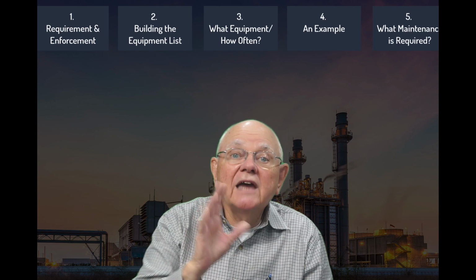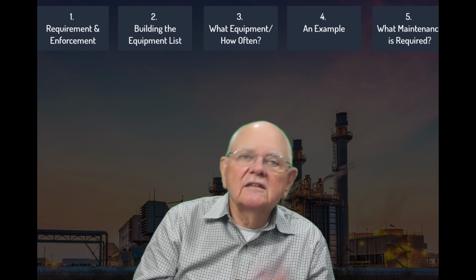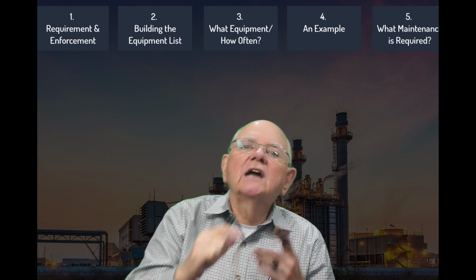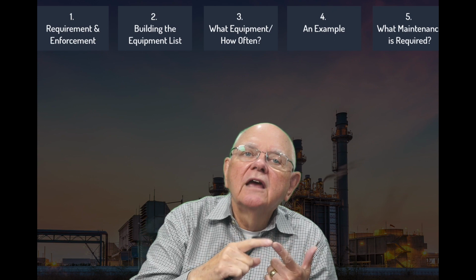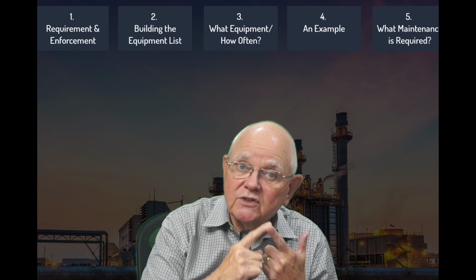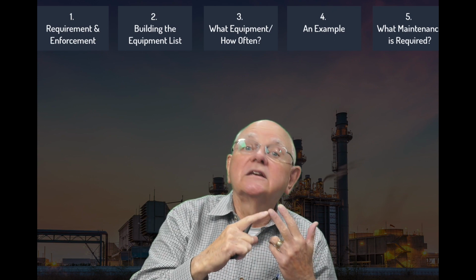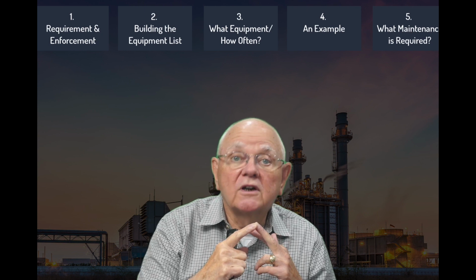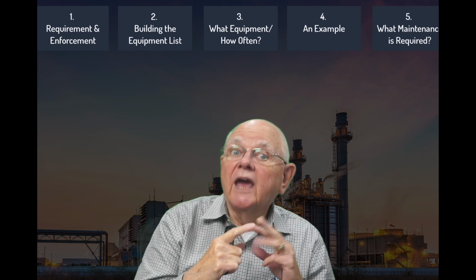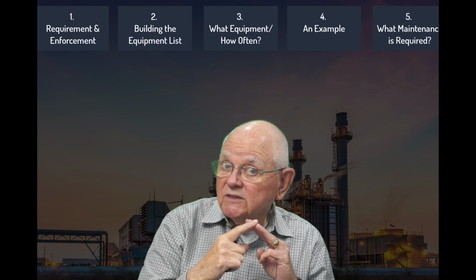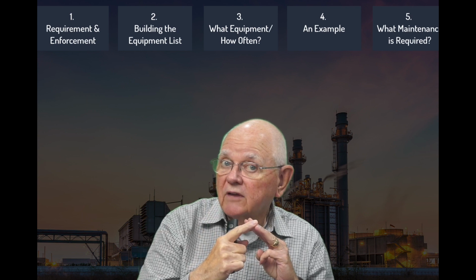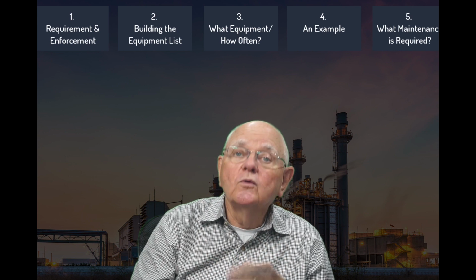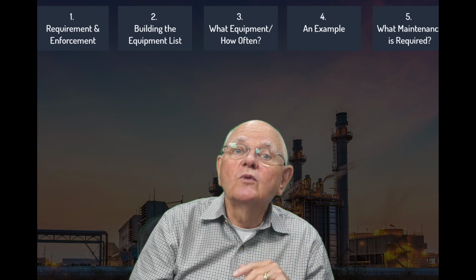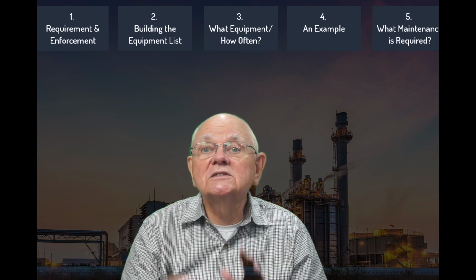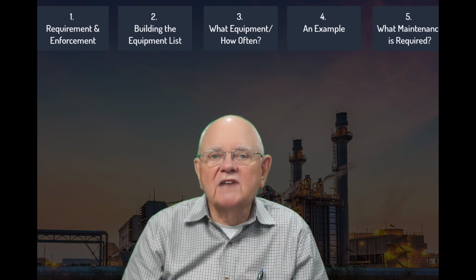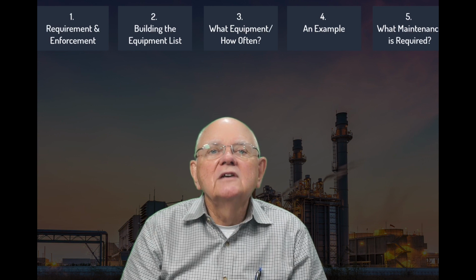So that's the highest number. Looking at this transformer, we assigned a 2 for physical condition, a 1 for operating environment, and because of its safety issue, a 3 for criticality. Therefore, when we go to do the maintenance, we'll do it in accordance with condition 3, since that's our highest number. So let's take a look.